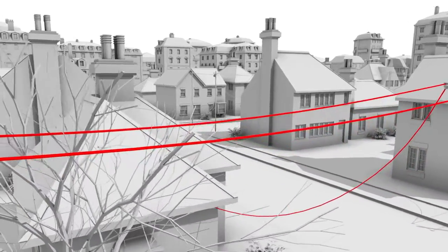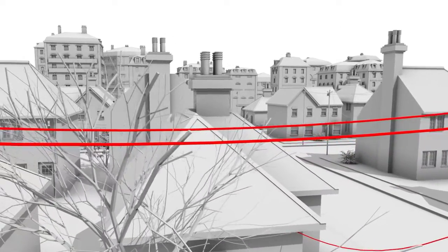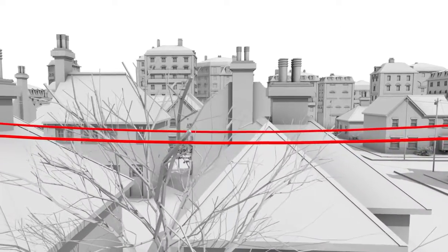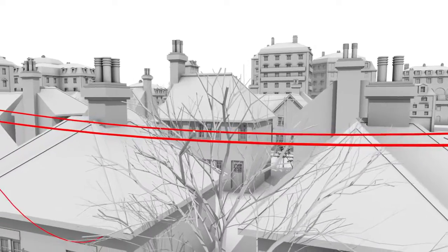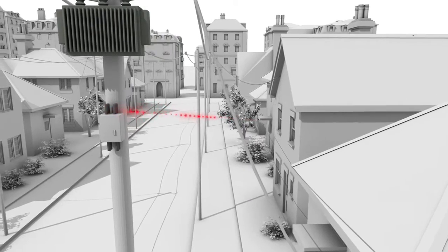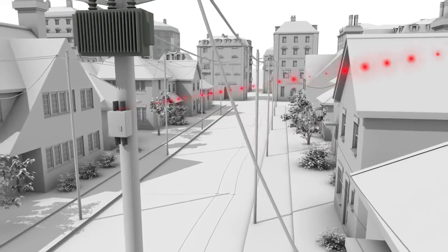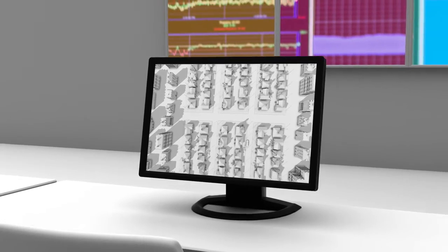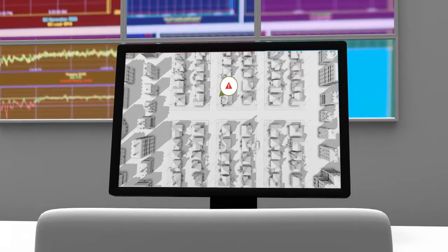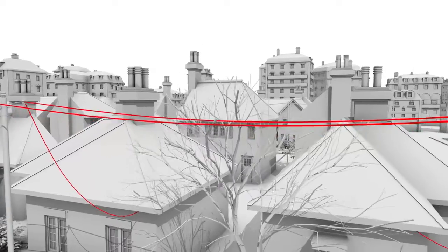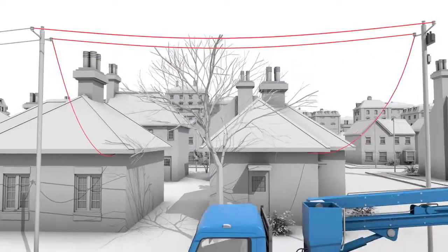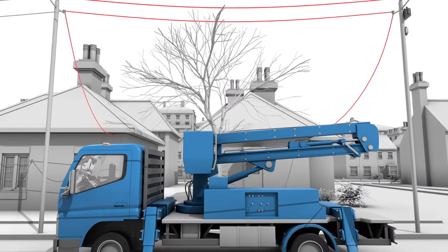In the event of a sudden change in impedance, often caused by failing connections or downed conductors, the OpenWay Riva application immediately sends a priority message to the utility, detailing the event and the location. By detecting and resolving potential safety issues before they become costly or dangerous problems, only OpenWay Riva saves utilities time and money and keeps your team and your customers safe.